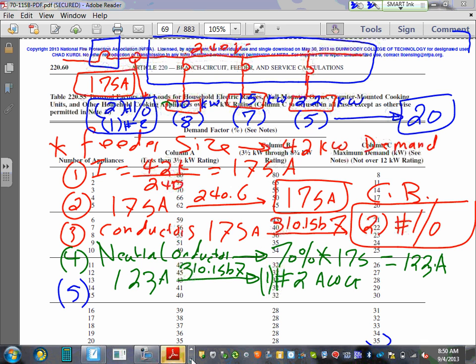Number 5, conduit size. Let's go size the conduit. I'm using EMT. This is a feeder, and the EMT is the equipment grounding conductor, so we're not putting a ground with it. We're just putting 2 hots and a neutral, and we're using the EMT as an equipment ground conductor. So I want you guys to see how the math is going to be.